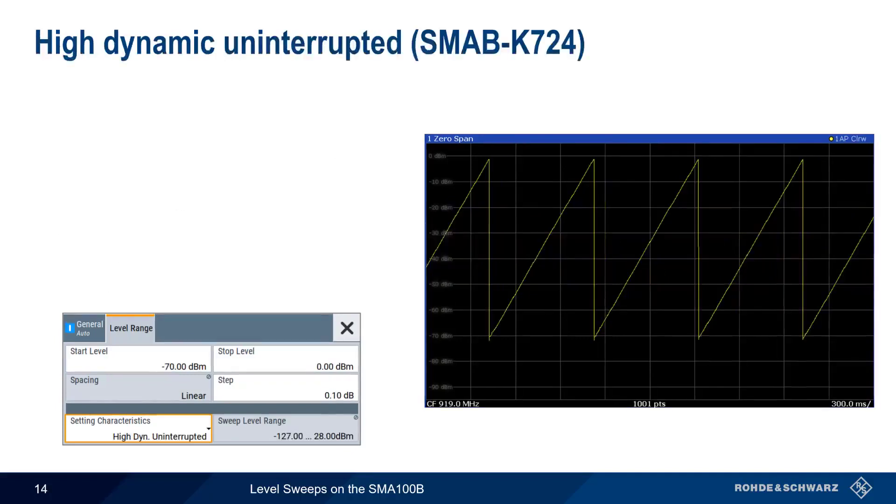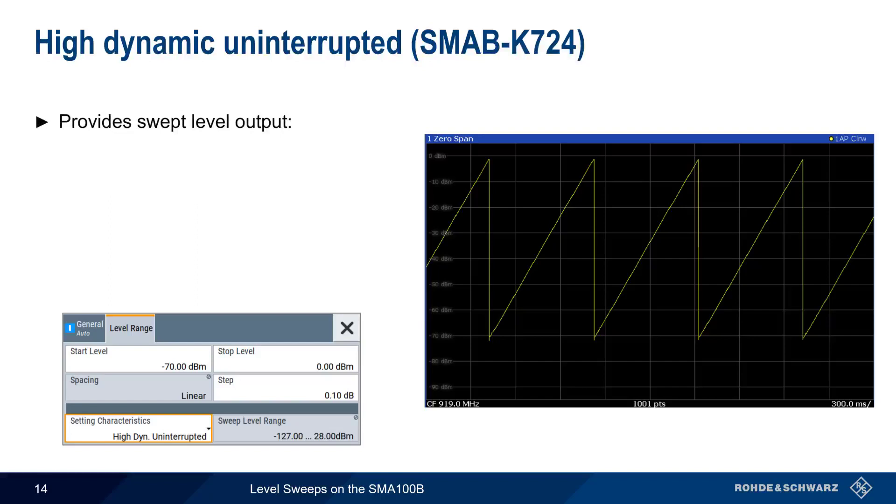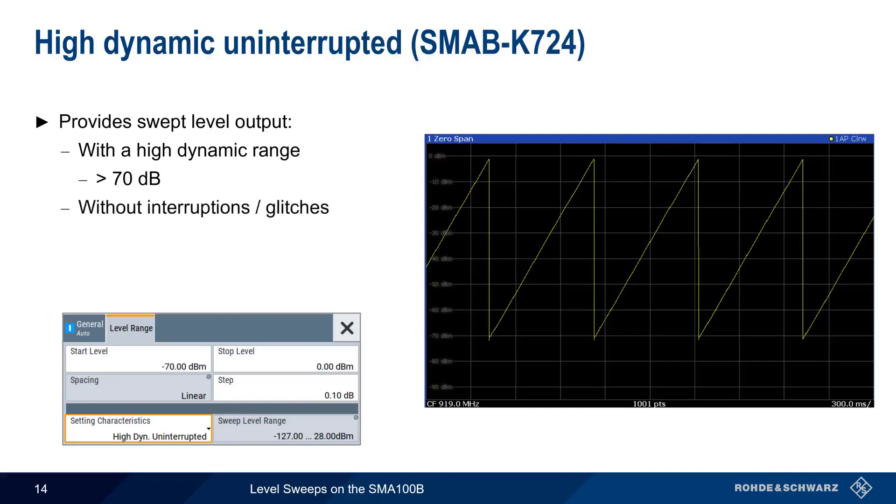As we discussed earlier in this presentation, high dynamic uninterrupted overcomes traditional limitations by providing a swept level output that has high dynamic range, 70 dB or more, and also does this without interruptions or glitches, as shown in the trace on the right. Note that the configurable sweep range in this case is over 100 dB.